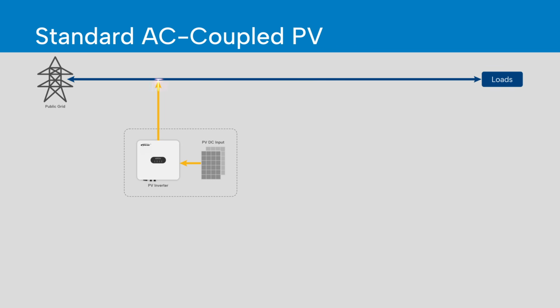We can add an AC-coupled PV system consisting of a grid-tied inverter and solar panels. If the load is higher than solar generation, all solar power goes to the load. If solar generation exceeds the load, the surplus is exported to the grid.